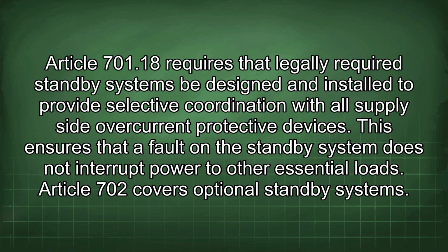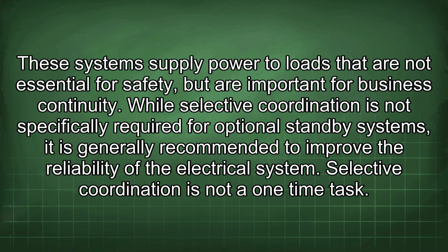Article 702 covers optional standby systems. These systems supply power to loads that are not essential for safety but are important for business continuity. While selective coordination is not specifically required for optional standby systems, it is generally recommended to improve the reliability of the electrical system. Selective coordination is not a one-time task.